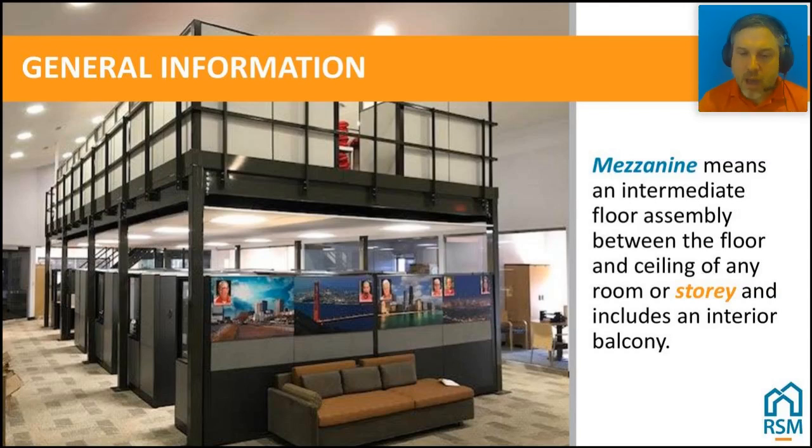In my past, I've had one car parts manufacturer that installed a mezzanine right in the middle of a huge plant, and then they kicked themselves into the requirements of having an exit. How are you going to get an exit which goes directly outside when you're in the middle of the plant? When you don't understand how mezzanines and code compliance are dealt with, you could get yourself into huge problems. So this is definitely something we need a good understanding of, especially if you get pressure to review these quickly and move them forward.